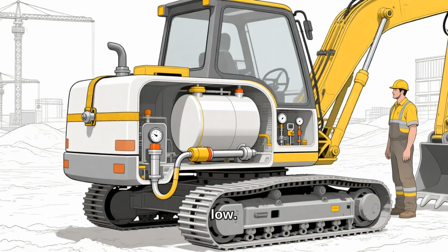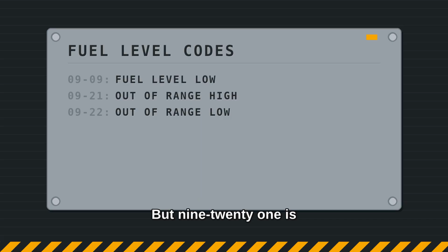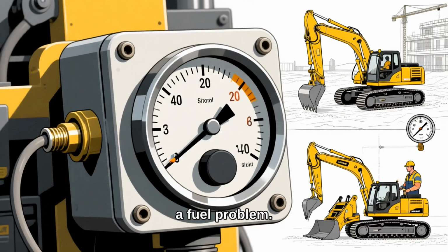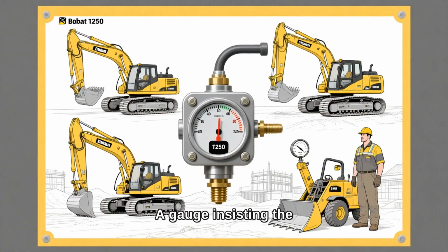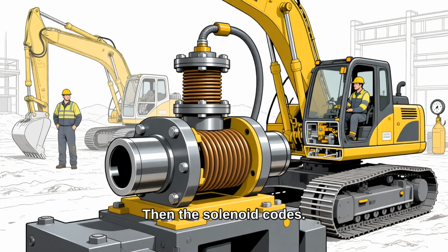99 is fuel level low. That one's honest, the tank really is getting empty. But 921 is fuel level out of range, high, and 922 is fuel level out of range, low. Out of range isn't a fuel problem. It's a reading the controller says can't possibly be real. A gauge insisting the tank is overfull is describing a sender circuit. It isn't describing diesel. Then the solenoid codes.